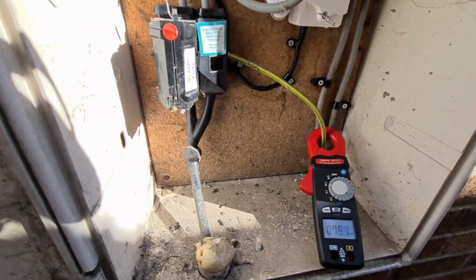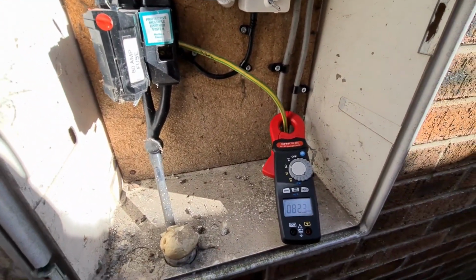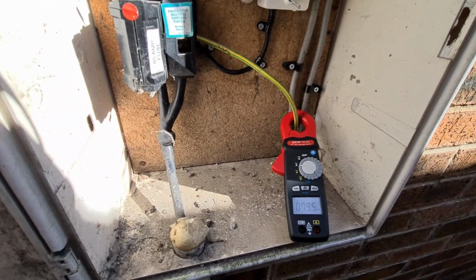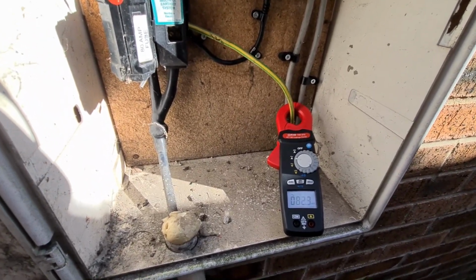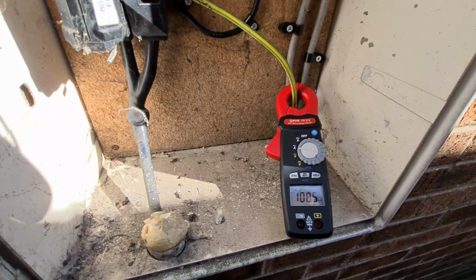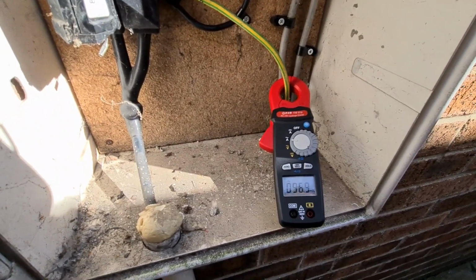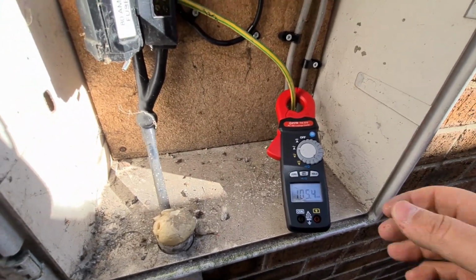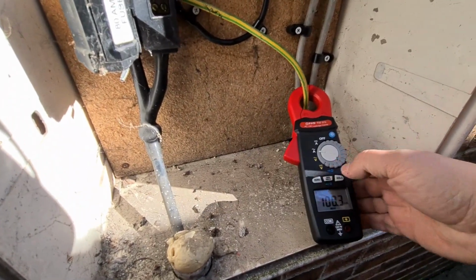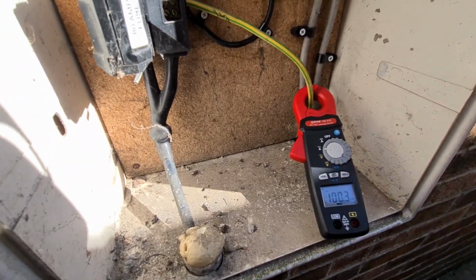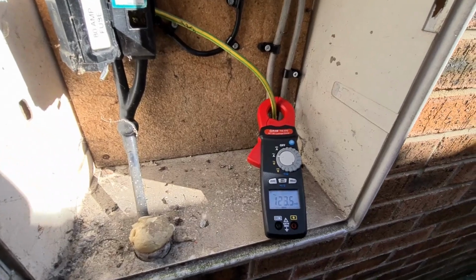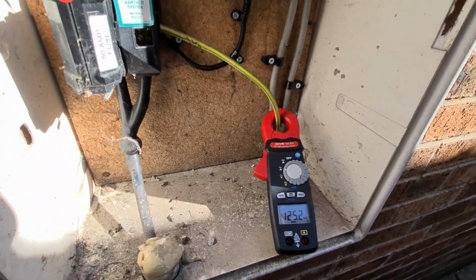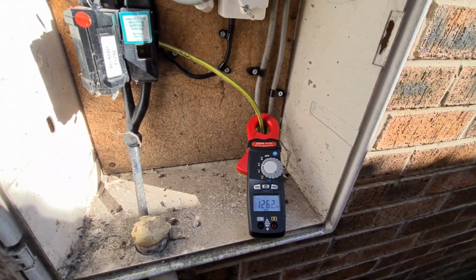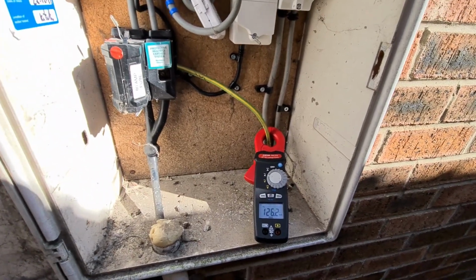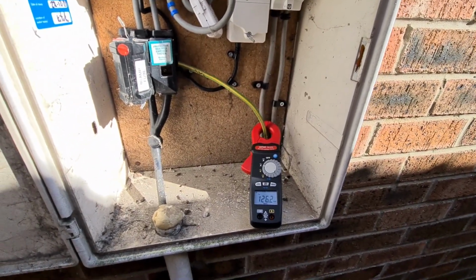This is the TIS 570 clamp meter - it's absolutely brilliant, this one. You can see it bouncing around there, so there's obviously something going on in a neighbouring property. I'll leave it sat on there and set it to do its max and min, just on the CPC - well, the main earth to the property - and see what maximum value it comes back with.